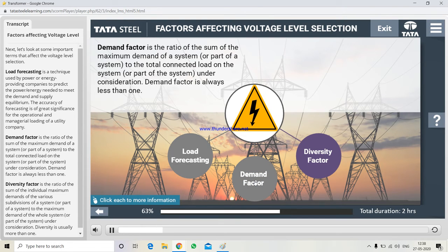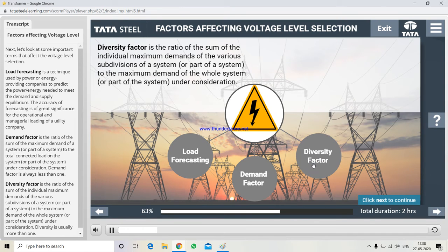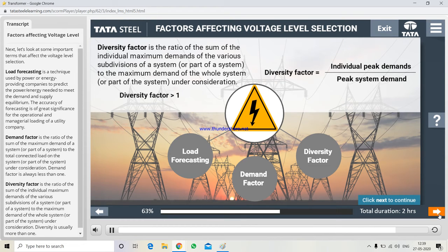Demand factor is the ratio of the sum of the maximum demand of a system or part of a system to the total connected load on the system or part of the system under consideration. Demand factor is always less than 1. Diversity factor is the ratio of the sum of the individual maximum demands of the various subdivisions of a system or part of a system to the maximum demand of the whole system or part of the system under consideration. Diversity is usually more than 1.